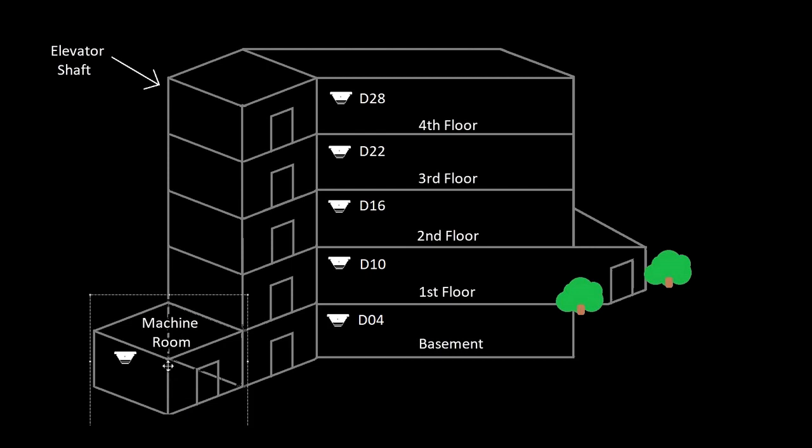Let's assume for now it's like this and it's located in the basement. If it's in the basement and there is a basement and your primary floor is the first floor, then this is kind of easy because we're just going to send the car to one even if the machine room detector goes off. You can flash the hat, send the car to one. To explain what I want to explain next, I'm going to have to get into the actual relays, so we'll be jumping around a little bit here back and forth, but I think you'll get the big picture idea easily enough. In the next video I'll probably look at the relays.